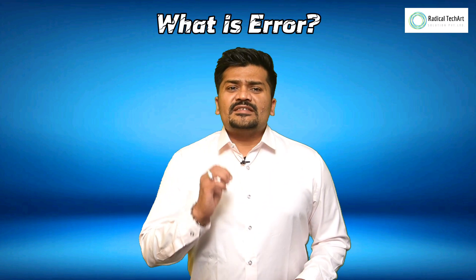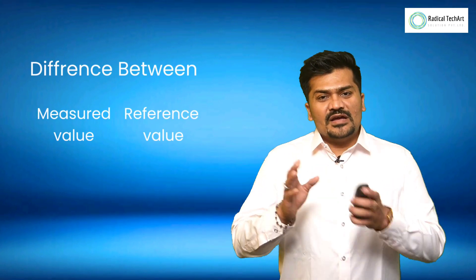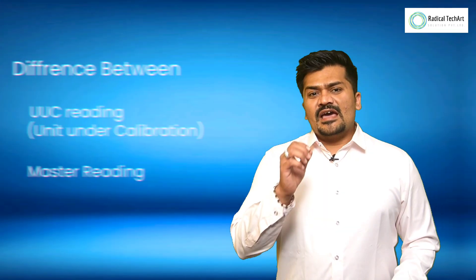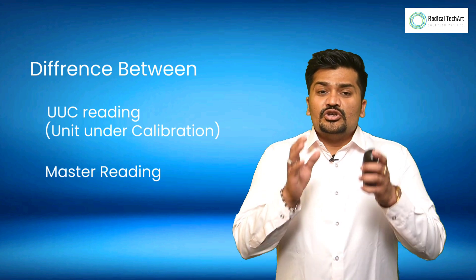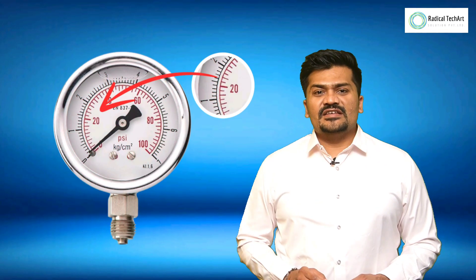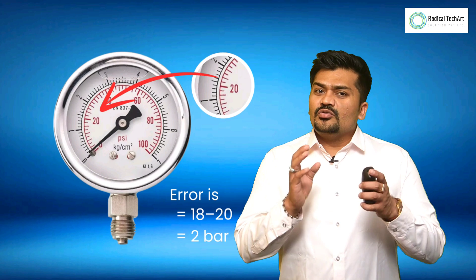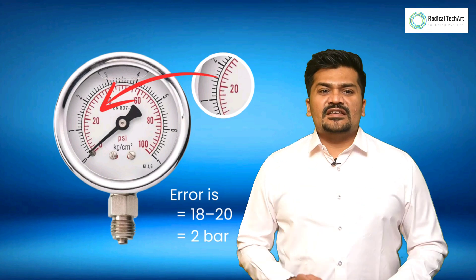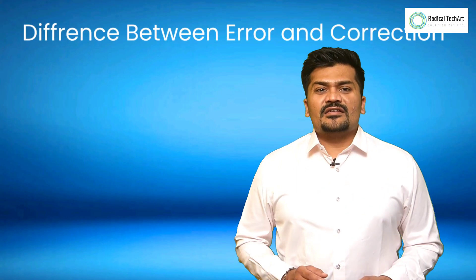Now let's see what is error. Error is the difference between the measured value and the reference value — that is, the difference between the unit under calibration reading and the calibration reference reading. For example, if the pressure gauge reads 20 bar but the unit under calibration reads 18 bar, then the error is 2 bar.